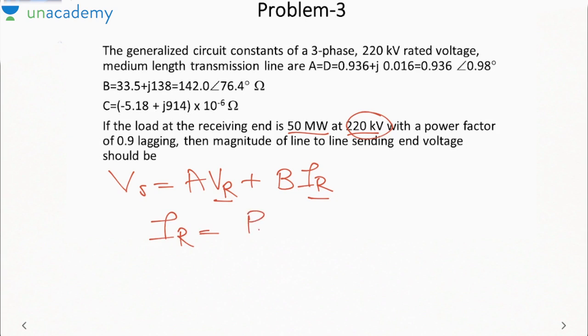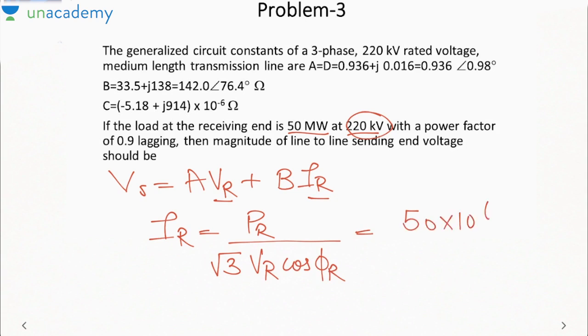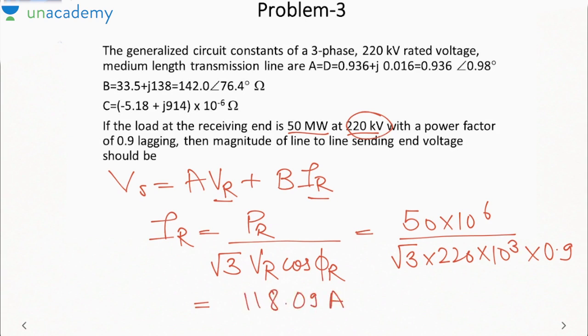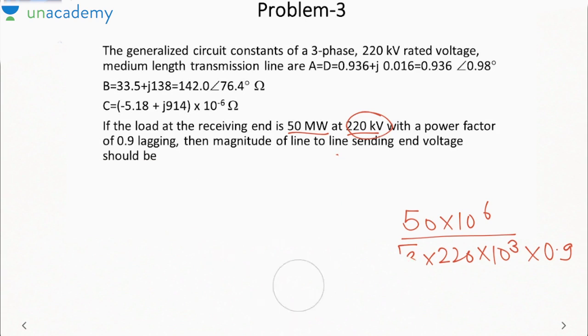So IR will be PR divided by root 3 VR cos phi R. PR is 50 megawatt, VR is given line to line as 220 kV, cos phi R is 0.9 lagging. This current comes out to be 118.09 ampere. One thing to remember is that whenever we apply this equation, it is applied on a per phase basis, that is, VR must be taken per phase.